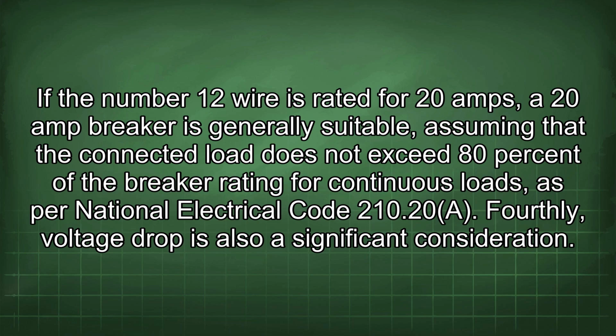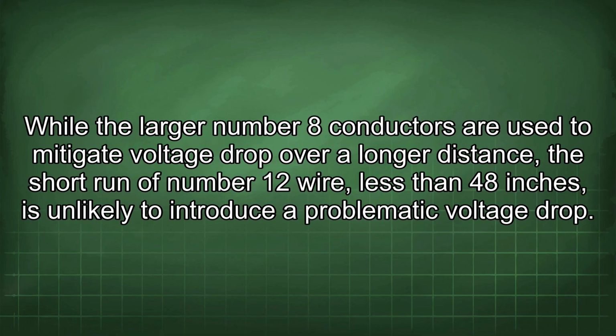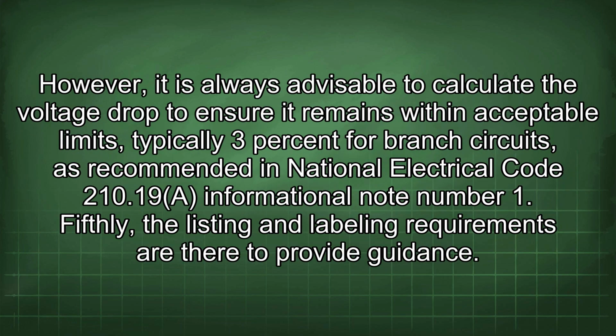Fourthly, voltage drop is also a significant consideration. While the larger number 8 conductors are used to mitigate voltage drop over a longer distance, the short run of number 12 wire, less than 48 inches, is unlikely to introduce a problematic voltage drop. However, it is always advisable to calculate the voltage drop to ensure it remains within acceptable limits, typically 3% for branch circuits, as recommended in National Electrical Code 210.19 Informational Note Number 1.